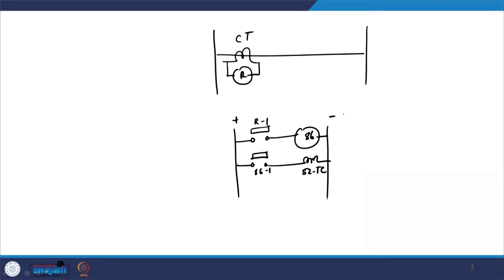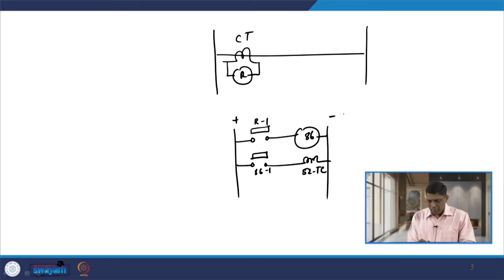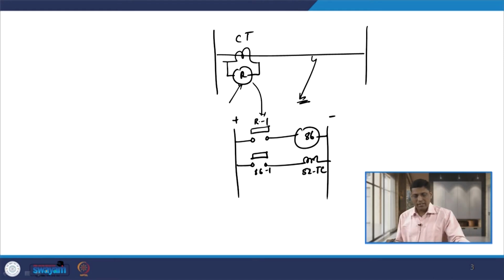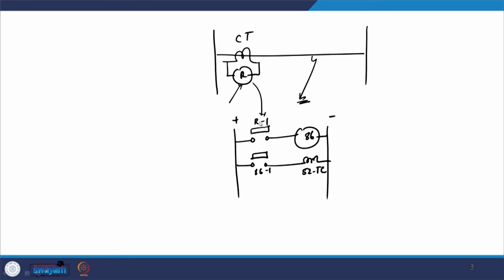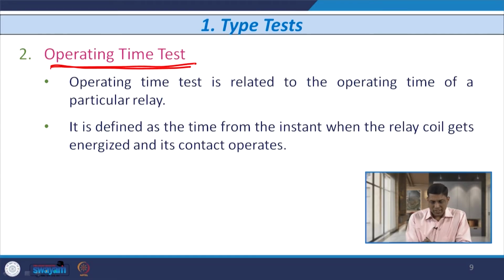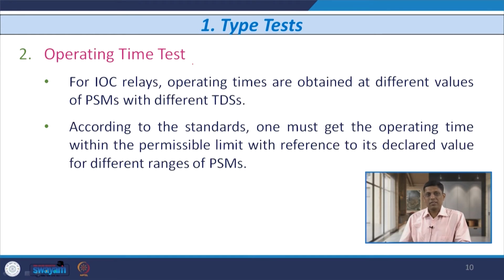So, this is your control circuit. Now, what is the operating time? Operating time means, as soon as the relay coil is energized, say some fault occurs, the current is transferred on the CT secondary side and flows through the relay, the relay coil is energized, and when it gives a signal to the relay contacts R1, that value is known as the operating time of the relay. For that we need to carry out the test that is performed by the manufacturer.